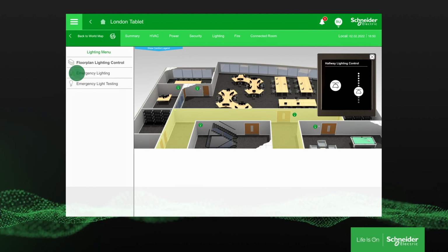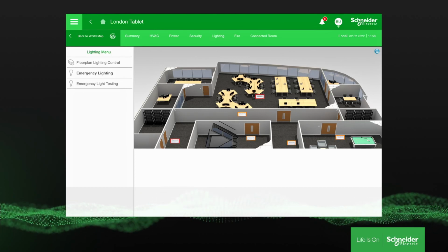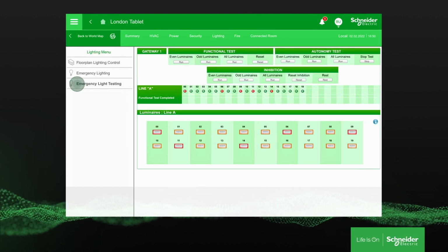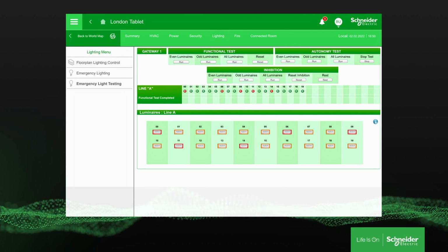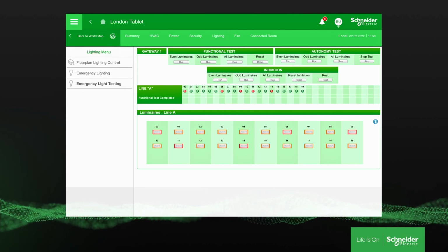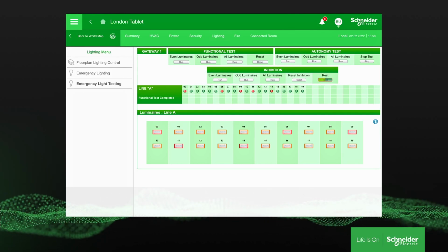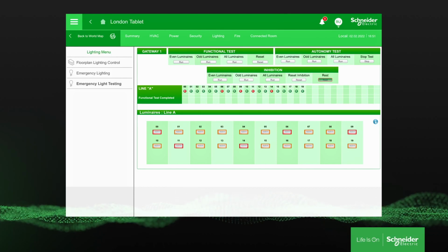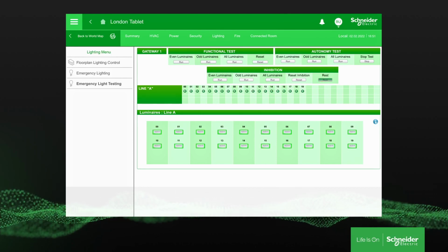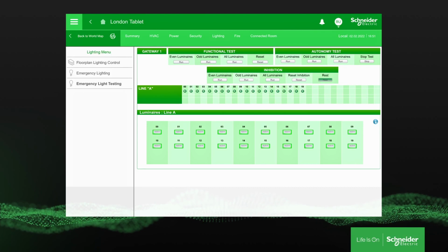Lighting integration includes full viewing and control of the emergency lighting. We can run a functional test on the full system. I see that I will also need to reset the alarm and acknowledge them to clear out my window, or focus in on the status of one lamp.